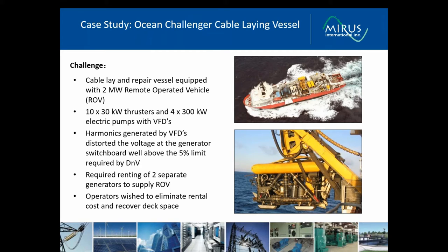This next application is an example of a cable laying vessel. It was equipped with, again, remote operated vehicles, or ROVs, that are used to walk the ocean floor, dig the trench, and lay in the cable. The ROV was equipped with various electric pumps and thrusters that were controlled by VFDs. These nonlinear loads increased the voltage distortion to levels above the mandatory limit of DNV, requiring the customer to isolate the loads by renting additional costly generators. And the generators that were added are shown here, these two white boxes, one for the port side, one for the starboard side ROVs. You can see that they occupy quite a significant amount of space, and there was certainly a significant cost associated with them.